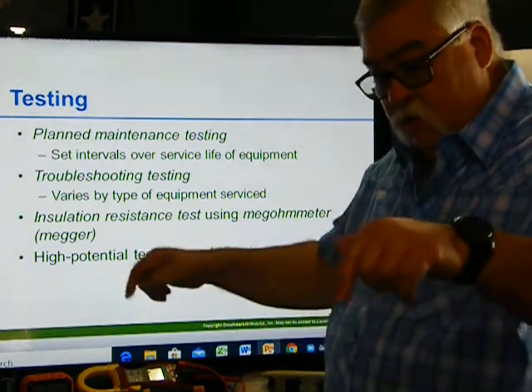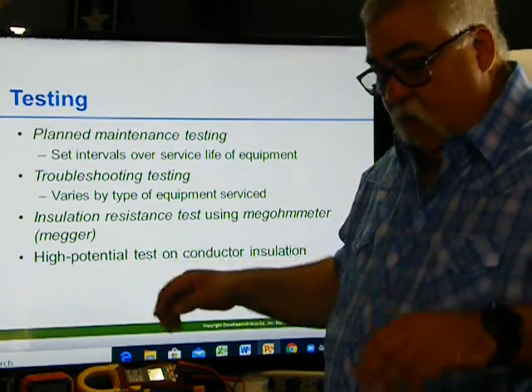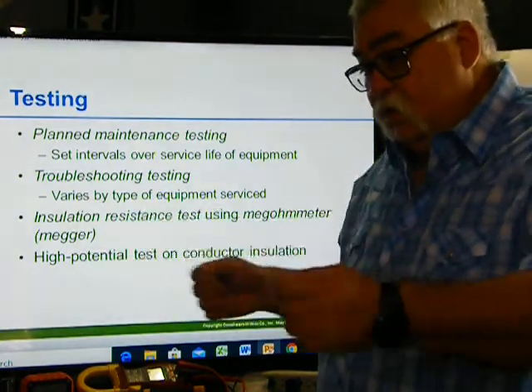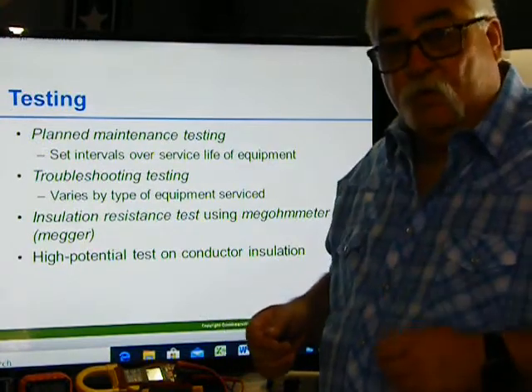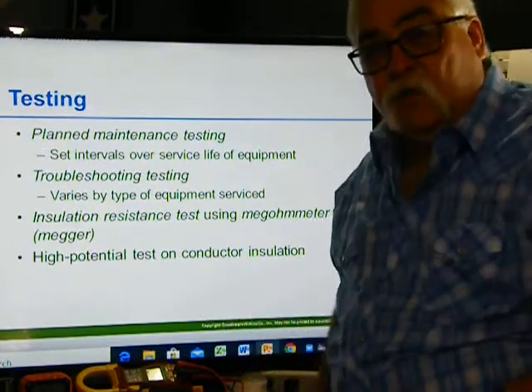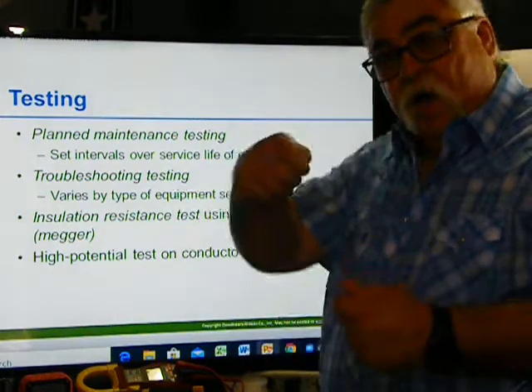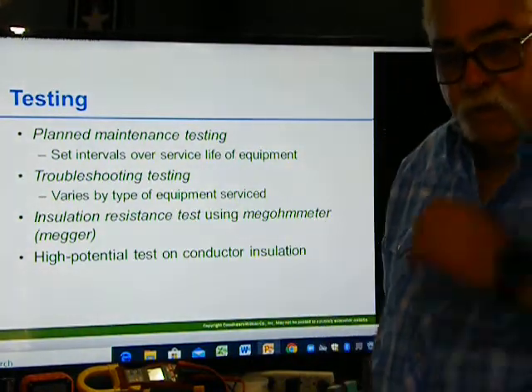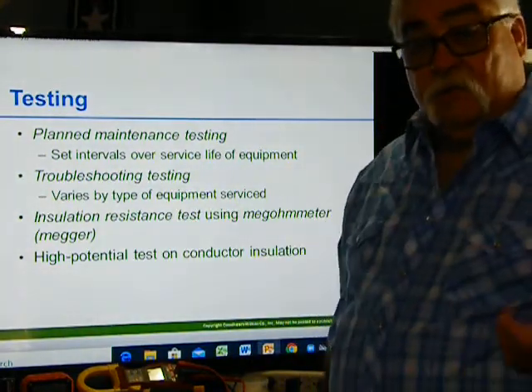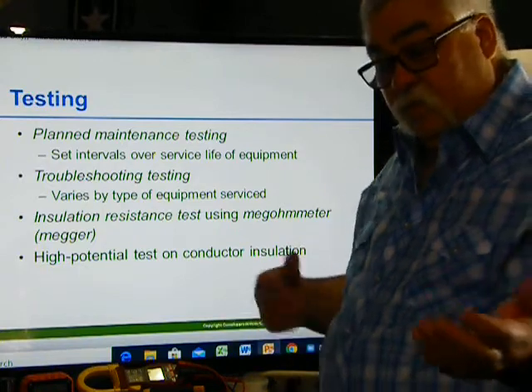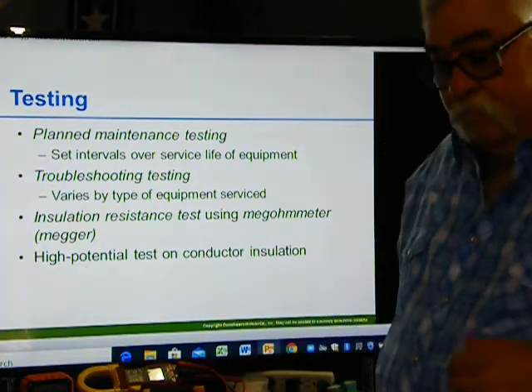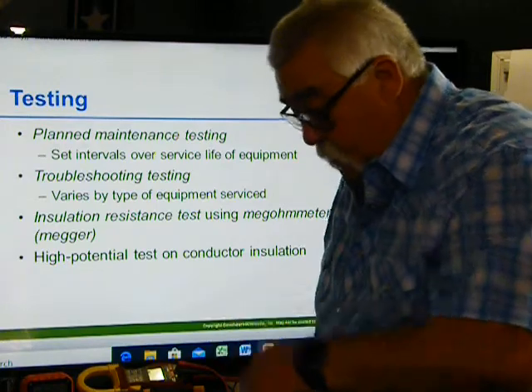And he's doing the equipotential testing. So he's going around testing everything. He's testing the ground rods. That's when he got the 5 ground rods, and he stuck them straight down, and then he tied in 120 volts to it to find out what the resistance was, so he can find out, because the code says you got to have 25 ohms or less to ground. I'm getting ahead of myself here.